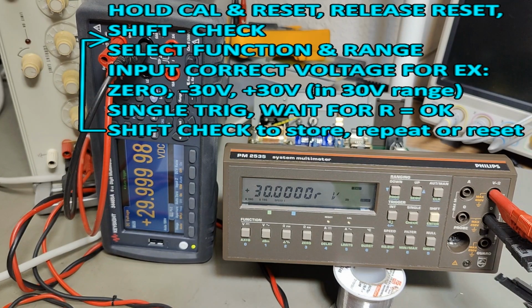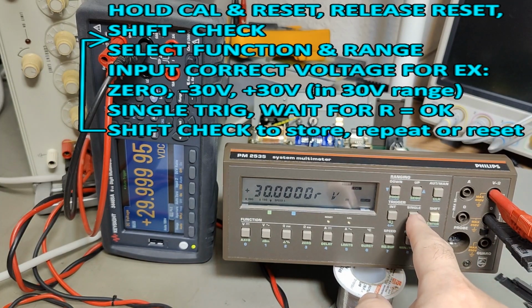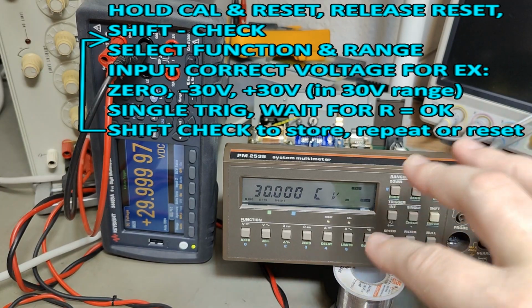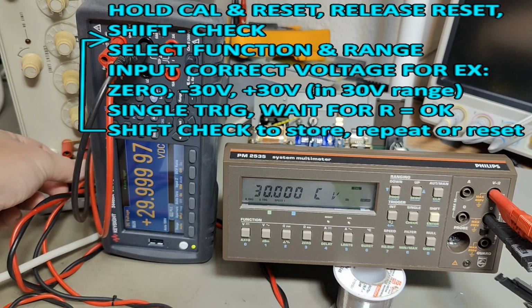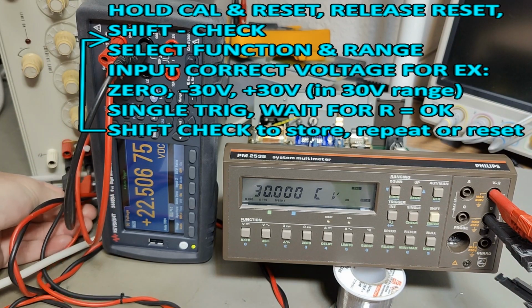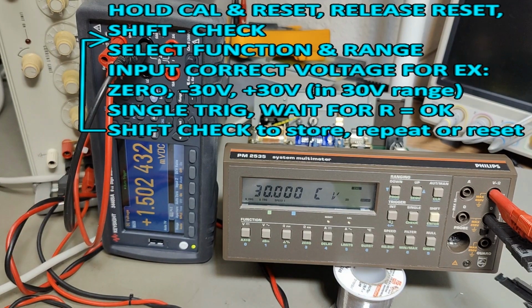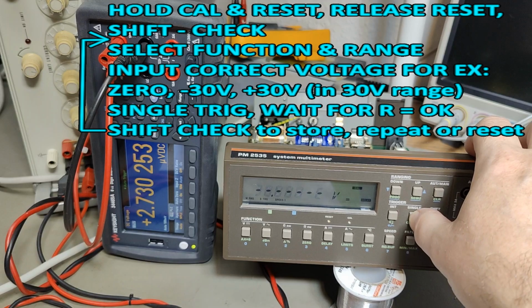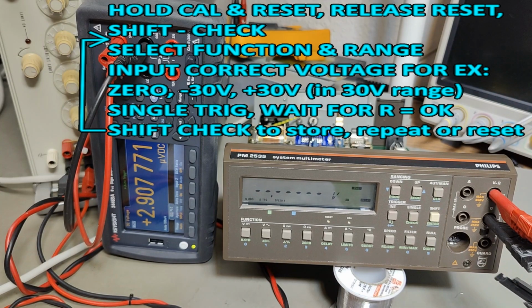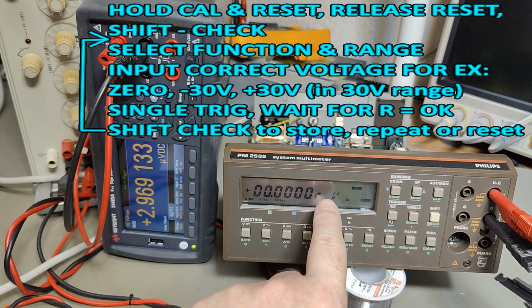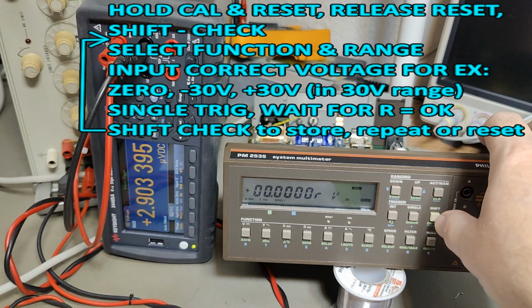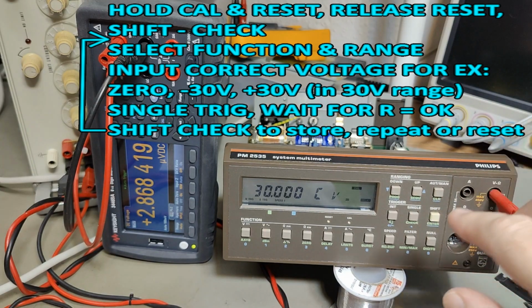So now I will shift check to store that calibration and then continue to the next calibration. So then I take my two inputs and then I short my two inputs to give you 0, of course, right? And then you just do the same. You single trig, and then it will now store the 0. Come on, come on, come on. It takes a little while, but otherwise you have to skip this part if calibration is not super important for you. And then it should say something about this R is the important when it has done it. And then, okay, shift check. Now we're ready to perform the next one.